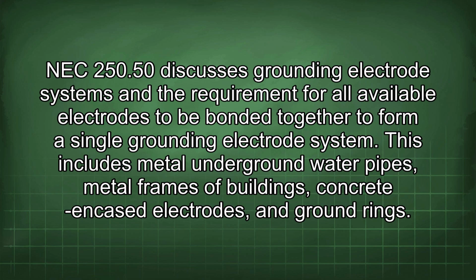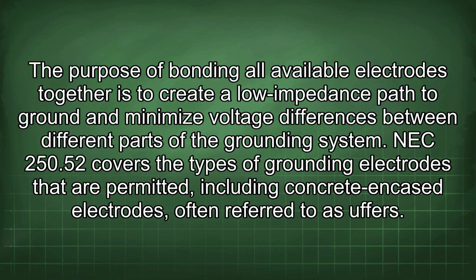This includes metal underground water pipes, metal frames of buildings, concrete encased electrodes, and ground rings. The purpose of bonding all available electrodes together is to create a low impedance path to ground and minimize voltage differences between different parts of the grounding system.